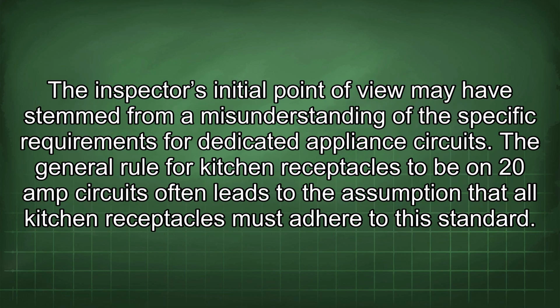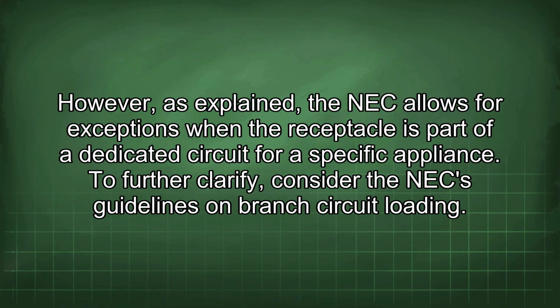The inspector's initial point of view may have stemmed from a misunderstanding of the specific requirements for dedicated appliance circuits. The general rule for kitchen receptacles to be on 20 amp circuits often leads to the assumption that all kitchen receptacles must adhere to this standard. However, as explained, the NEC allows for exceptions when the receptacle is part of a dedicated circuit for a specific appliance.